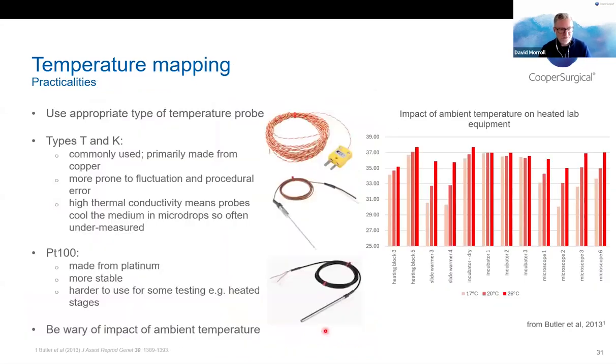Now, you can do a whole raft of temperature mapping, and as we've suggested, your incubators and your heated stages need to be tested. Just be aware that there are different impacts of different probes. We typically see type T and type K thermocouples, that's these two here. These are made primarily of copper, and copper is a fantastic conductor, which means that it's very sensitive, but it also means it's very prone to fluctuation and procedural errors. So if you use a thermocouple like this and it has a tiny exposed wire at the end, that's the bit that you might typically put into microdrops when you're testing. But if the rest of the thermocouple is cooling, you might be under measuring. So you just have to be really careful that you're not under measuring with that sort of system.